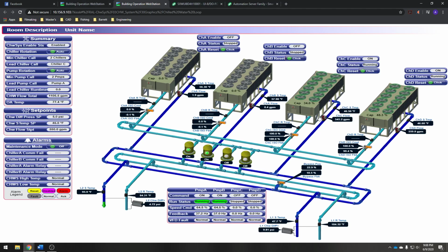we control the chillers? So let's say for whatever reason we need to make sure chiller A turns on. Let's say C died, the auto program did not run, something is majorly wrong. Let's say both of these chillers then die, something's wrong with the pumps, these chillers go out on loss of flow, whatever the case may be. This is how you actually interface with this system to turn chiller 1 on.